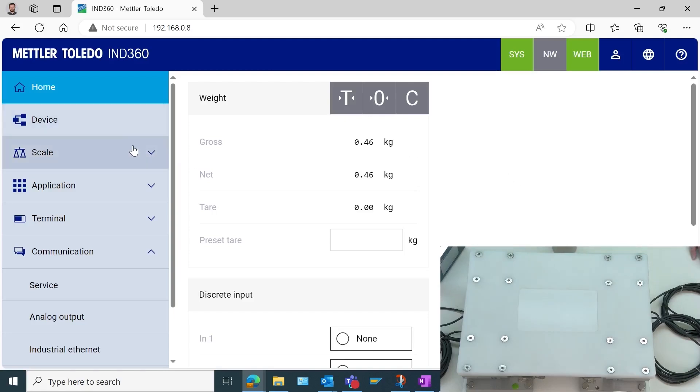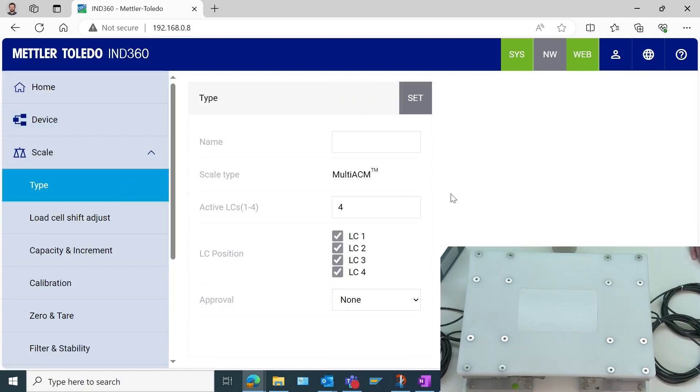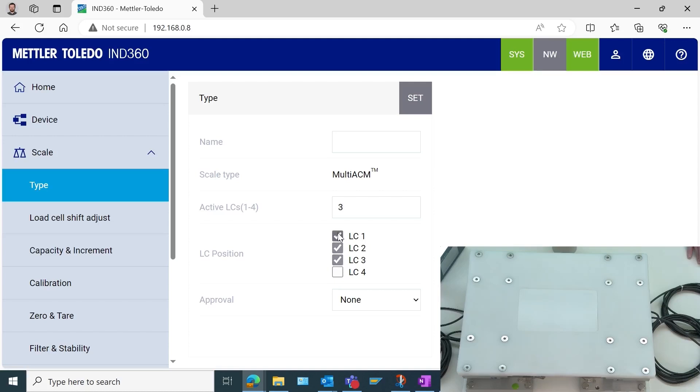To do that, I'm going to go to scale and then type. What I want to do is enter in the number of active load cells. So in this case, it is 4. If for example, I had 3, then we would just need to select checkboxes for which of the load cells we had wired in. But since it's 4, it'll automatically populate all 4 of these. So I'll go ahead and select set.